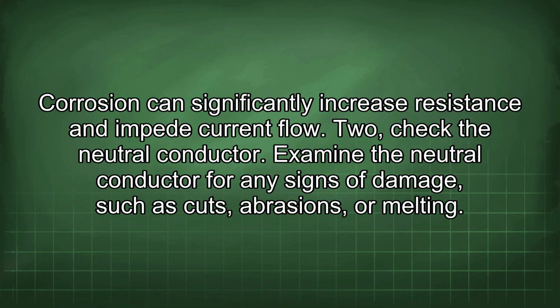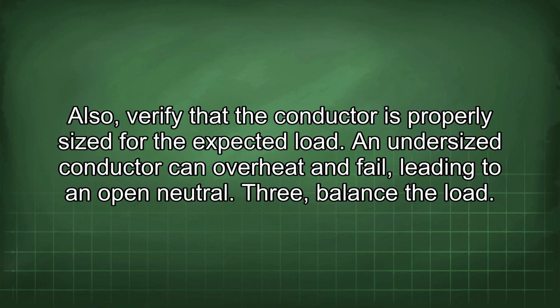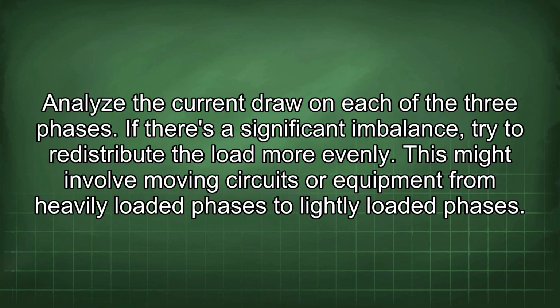2. Check the neutral conductor. Examine the neutral conductor for any signs of damage such as cuts, abrasions, or melting. Also, verify that the conductor is properly sized for the expected load. An undersized conductor can overheat and fail, leading to an open neutral. 3. Balance the load. Analyze the current draw on each of the three phases. If there is a significant imbalance, try to redistribute the load more evenly. This might involve moving circuits or equipment from heavily loaded phases to lightly loaded phases.